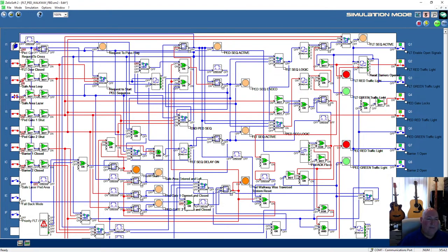So let's now the pedestrian. Now it's timed out, but that's good because it means that I'm still in the safe area. So it won't allow me through, but it's not active. So the ped gates are locked now, and I might be stuck there. So this is where we need to differentiate this laser from the laser at the pedestrian area and a forklift truck. That's why we've got another area, just the width of the pedestrian area, so we can tell if there's anyone in the pedestrian crossing area, rather than the full area going right up to the roller shutter door. So it's sat there waiting, and I can't get out at the minute.